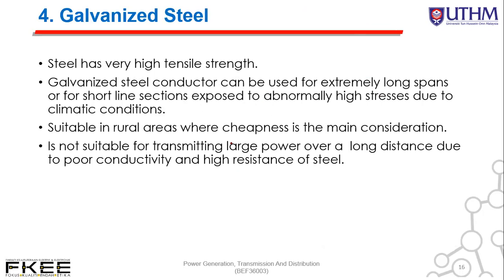Now we see the galvanized steel. Steel has very high tensile strength, which is good. Galvanized steel conductor can be used for long spans or for short line sections exposed to abnormally high stresses due to climatic conditions, and is also suitable in rural areas where cheapness is the main consideration. Of course, steel is cheaper than aluminum and copper. It is not suitable for transmitting large power over a long distance due to poor conductivity. Steel has poor conductivity and also high resistance.